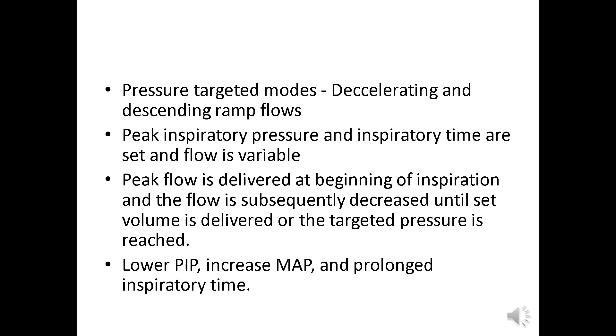In pressure-targeted mode, there is a decelerating and descending ramp flow. The peak inspiratory pressure and inspiratory time are set, so the flow is variable. The peak flow is delivered at the beginning of inspiration and subsequently decreases until the set volume is delivered or the target pressure is reached. This results in a lower peak inspiratory pressure, increased mean airway pressure, and prolonged inspiratory time.